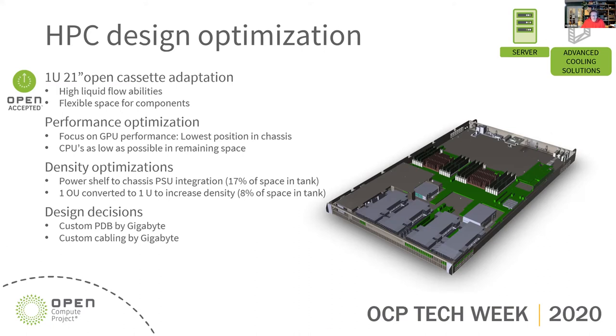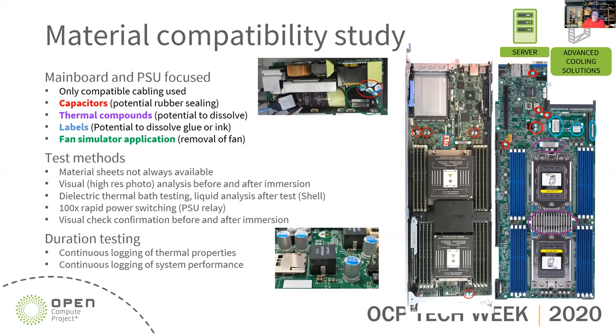In all these collaborations, before even touching liquid, the very first thing addressed with physical materials is material compatibility. In every platform we document exactly where suspect materials can be found. Most of the time we look out for capacitors, thermal compounds, labels, and fan simulator applications. Power supplies very often cannot operate without fans present, but you don't want fans in an immersed system. Cutting off those fans and applying fan simulators — which are also part of the OCP specs — is one way to deal with that.